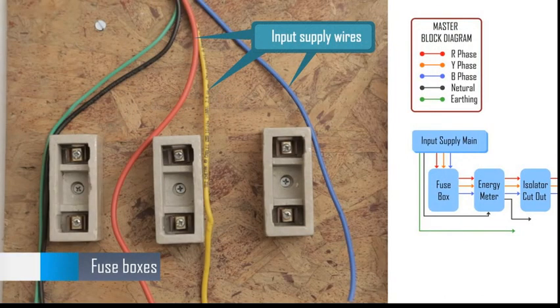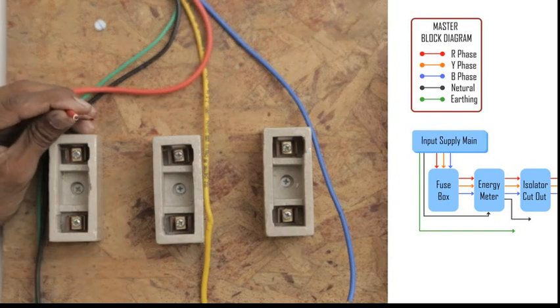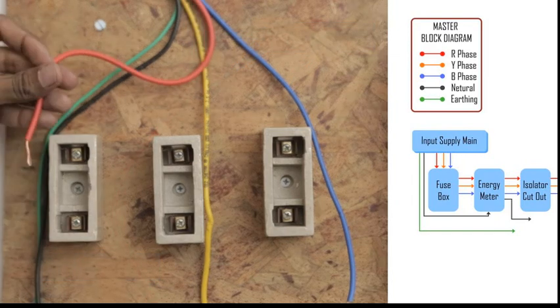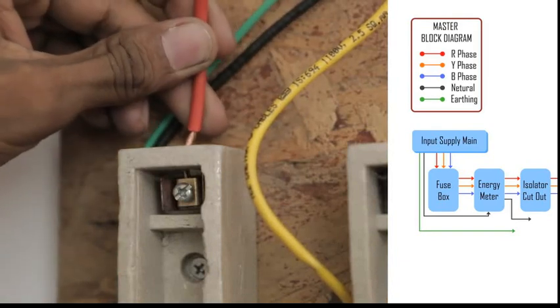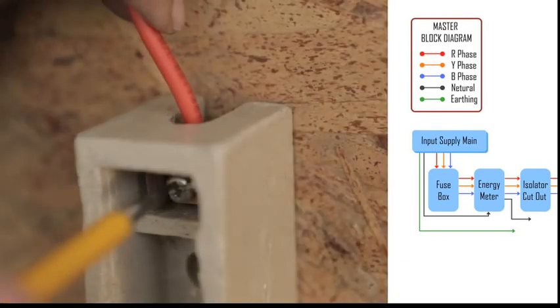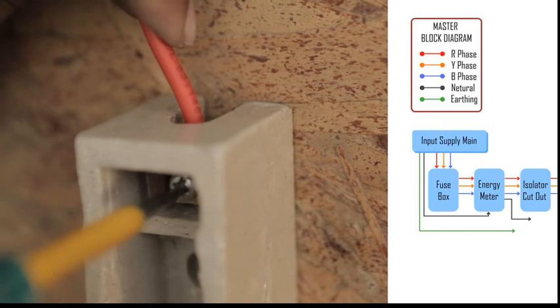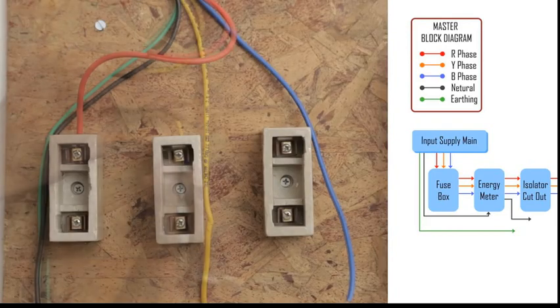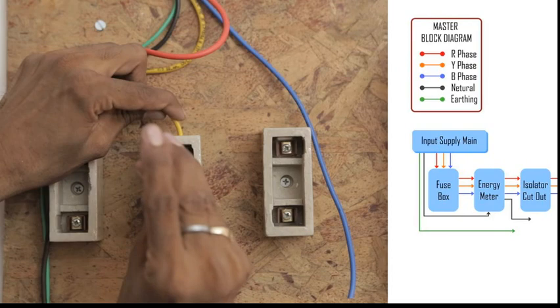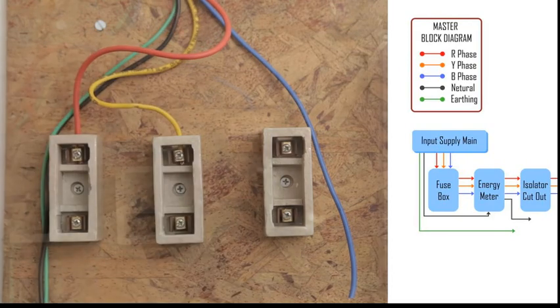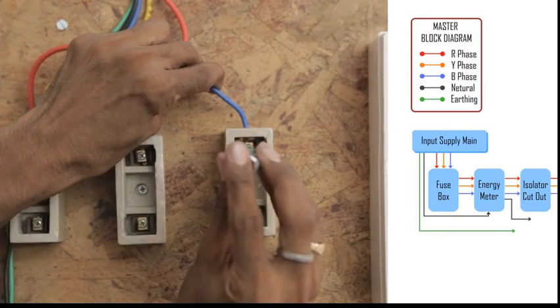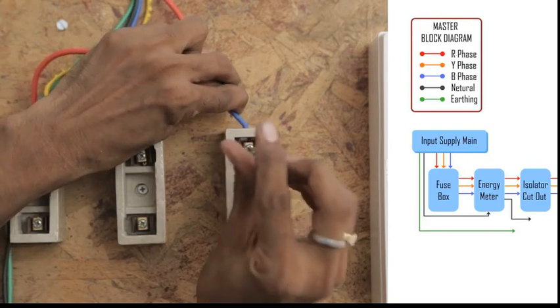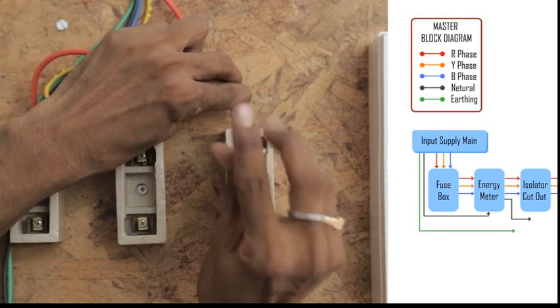First, connect the input supply wires from the main to the input terminals of all the fuse boxes. Start by connecting the R of the main to the first fuse box. Similarly, connect the Y and the B of the main to the input of the second and the third fuse box. Using a suitable screwdriver, tighten the wire connections.